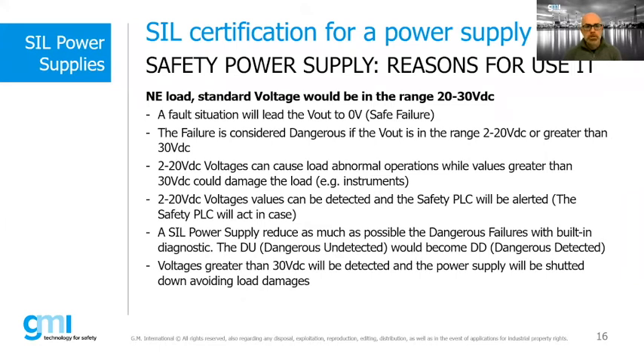At this point, why is it important to use a safety power supply system? First of all, we know that the standard voltage for a normally energized load is in the 20-30 volt DC range. As we have seen previously, conditions that lead to power supply output voltages between 2 and 20 volt and higher than 30 volt are considered dangerous failures, which negatively affect the application.